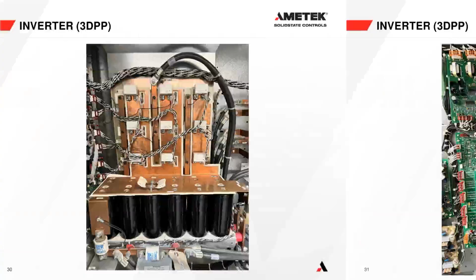One thing I didn't show you on this last picture: these are snubber capacitors, but behind these terminals you can see the white module, and it actually goes all the way back here. So there's one IGBT module there, one IGBT module there, and one IGBT module there, and that's the same for each of the phases.